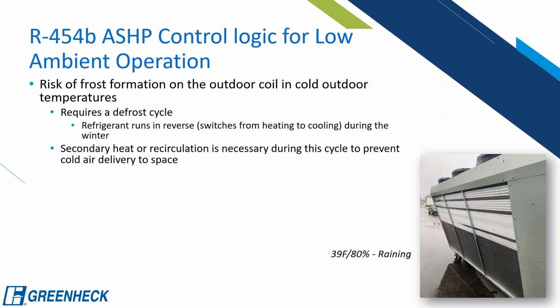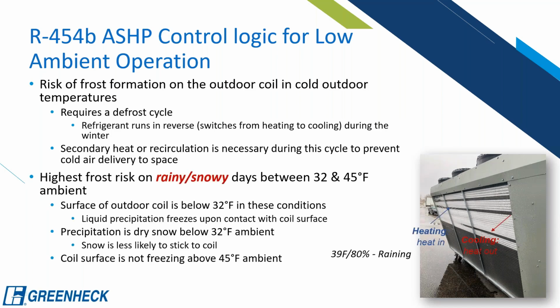With control logic for low ambient condition, let me push this through. With the defrost cycle, it does switch from heating to cooling. And this is when you would need the secondary heat or recirculation during that cycle to prevent cold air delivery to the space. And really, that's only a risk during rainy or snowy days between 32 to 45 degrees. If it's below 32 degrees, that snow will be less likely to stick to the coil. And if it's above 45 degrees, there's nothing that's going to freeze on top of it. It really would just be rain that sticks to it otherwise.